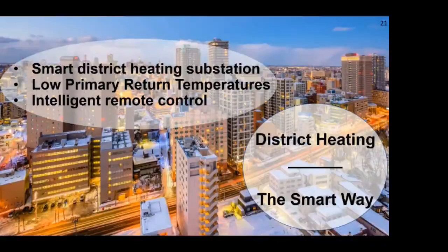Can you achieve weather compensation? Yes, if the system is monitored, with a heat network, a heat station, or even a large boiler system. It's about monitoring and understanding what's going through, and where your hot water is being used. Can it be reduced to a slightly lower temperature, again taking into consideration Legionella and things like that? With your heating, can you lower your temperatures even in the winter?